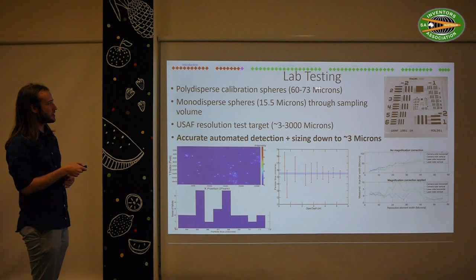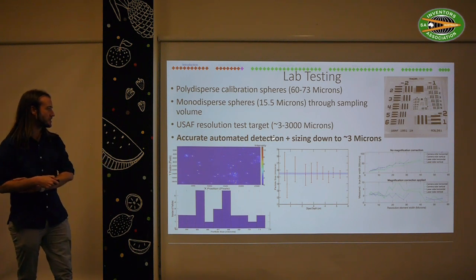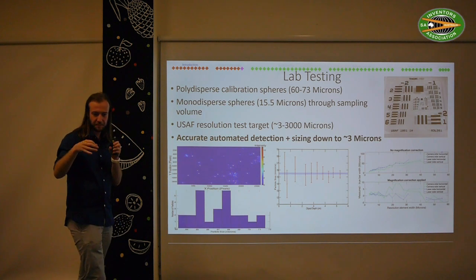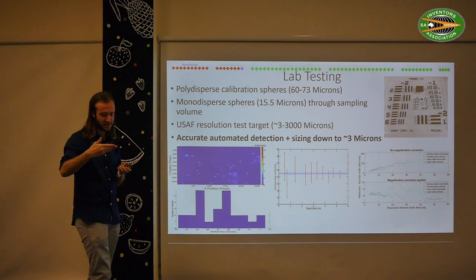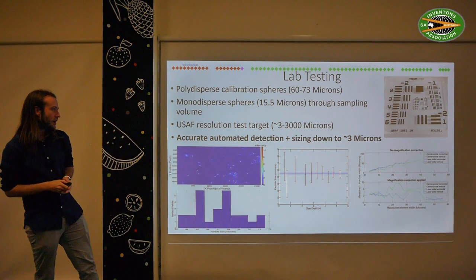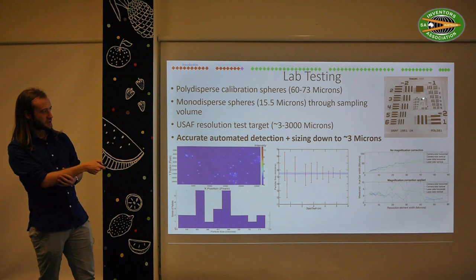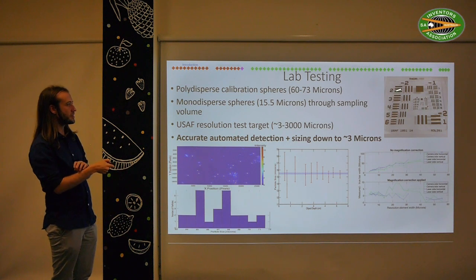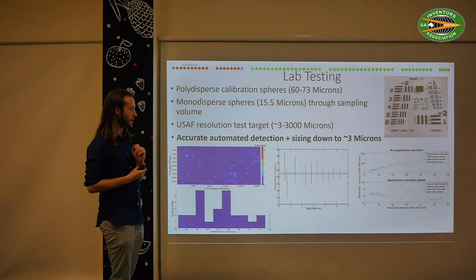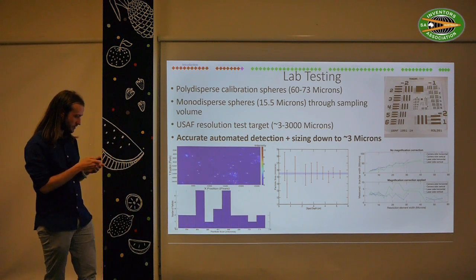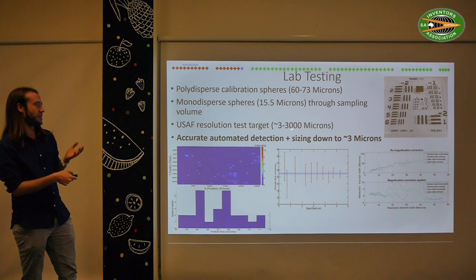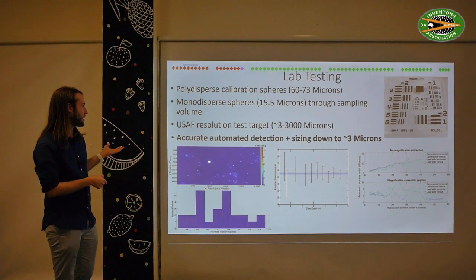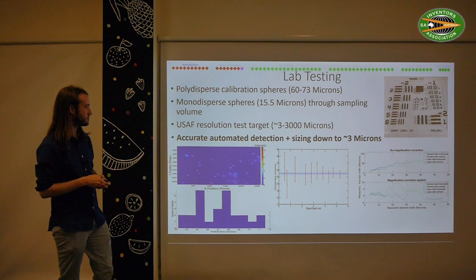We've done extensive lab testing on these instruments using calibration microspheres — particles where you absolutely know the size — which you put through your sampling volume to test you're measuring what you think you're measuring. We've also used US Air Force resolution test targets, which go all the way down to just a couple of microns up to a few millimetres. This gives us a great way to calibrate and validate our lab observations. We've confirmed the size range: we can measure particles from about 3 microns up to about 3 millimetres, and the automated analysis can handle these size ranges.